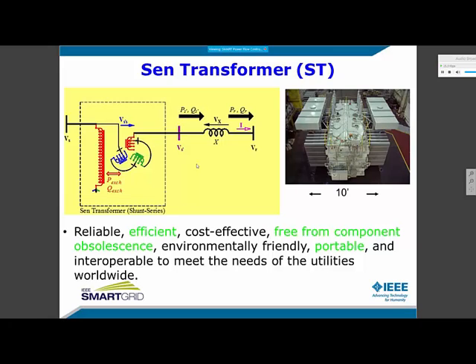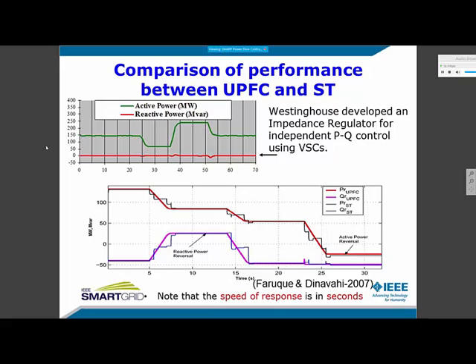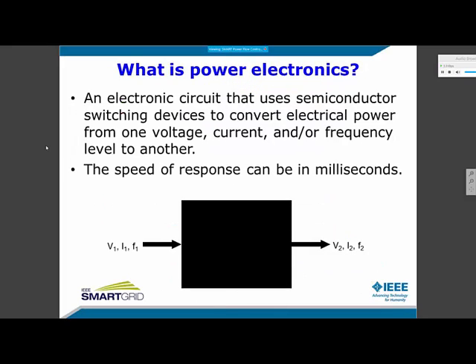Please note that an inverter-based power flow controller cannot operate, and I stress, cannot operate in all of its available power flow control range. The ST is the only power flow controller that can be designed to keep the power flow control area to what is needed, eliminating the waste and resulting in a low-cost power flow controller. Power flow in a line can be reduced by making the line impedance higher than its natural value, or increased by making the line impedance lower than its natural value.